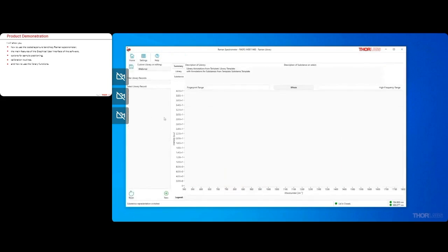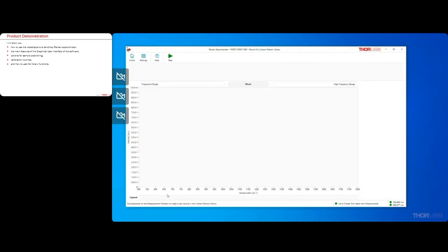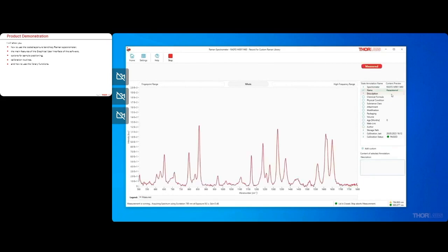We now add a new sample measurement by clicking on the plus icon and starting the measurement. While we wait for the measurement to be finished, we can already edit the sample name and the description as required fields. We also recommend adding other information about the sample if it is available.